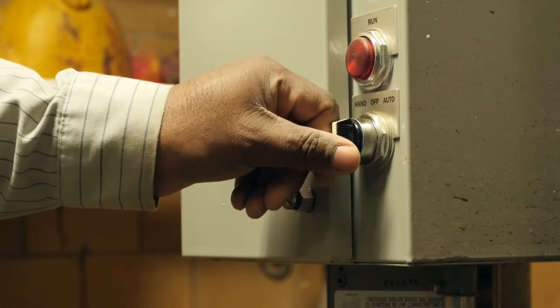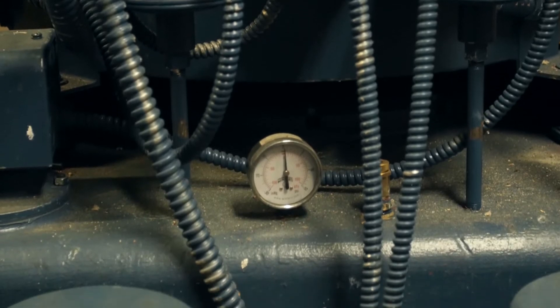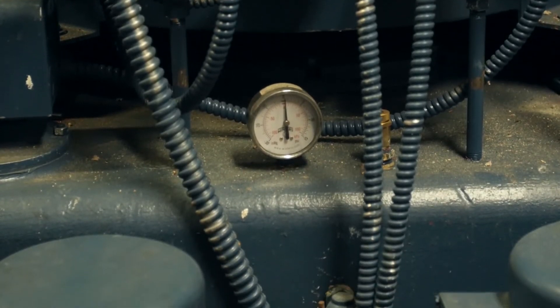We said that's unacceptable. We got a PRV station working, and because of the traps and the new kind of safe vacuum pump, we managed to keep the building running now all year long with about a pound or two for the building, and we still managed to keep 12 pounds for the absorber when we need it.